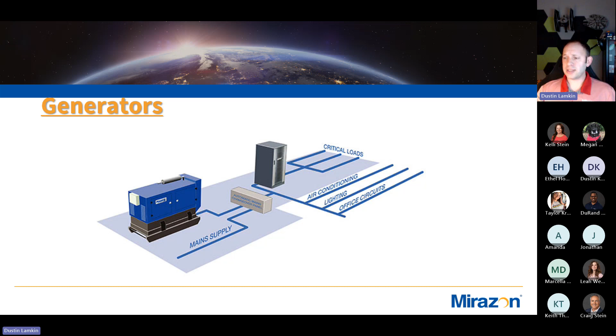So we talked about a lot of this. Generators are for long-term power outages, UPSs for short-term power outages. The big difference is UPSs are fast to flip over power - even the desktops, they're 1 second. The generators can take minutes to kick in, they're a lot of work. Even if they're automatic, they're going to be 30 seconds to kick in for a good automated system.